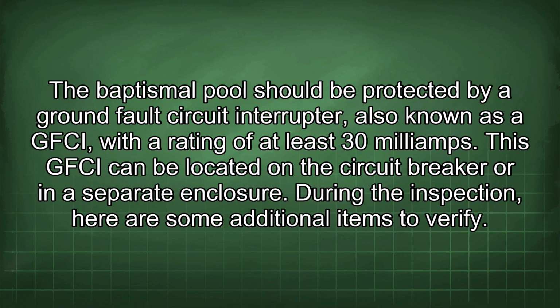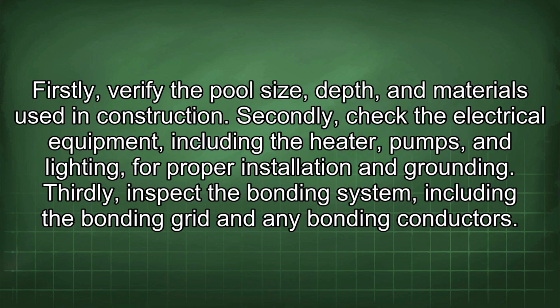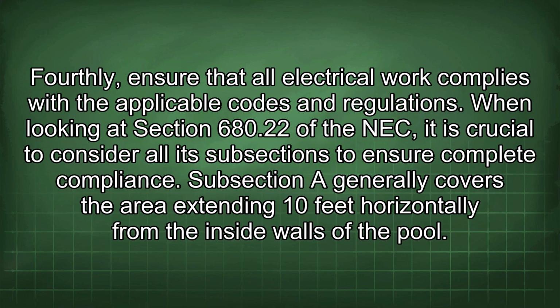During the inspection, here are some additional items to verify. Firstly, verify the pool size, depth, and materials used in construction. Secondly, check the electrical equipment, including the heater, pumps, and lighting, for proper installation and grounding. Thirdly, inspect the bonding system, including the bonding grid and any bonding conductors. Fourthly, ensure that all electrical work complies with the applicable codes and regulations.